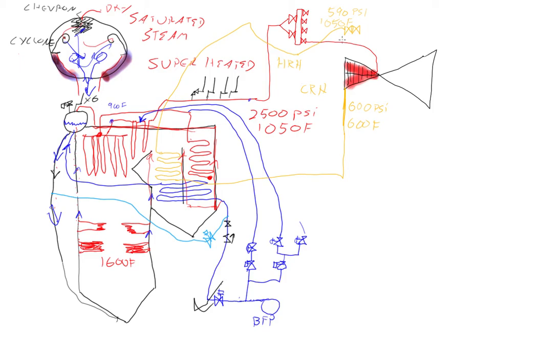How do we control that set point of 1,050? If you remember back on the main steam side, we sprayed attemperators in between the primary and secondary and in between the tertiary and final, and that knocked that temperature down to our target of 1,050. Do we spray water into the cold reheat to control the hot reheat at 1,050? Yes we do.